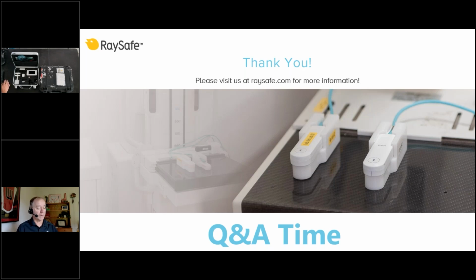But it is versatile enough too, right? So if we have, for instance, a tomo exposure from mammography, there's a setup pulse, and then there's what I call the real part of the exposure, right? And you want to accumulate dose, for example, in both the setup pulse and the real part of the exposure. So you can set the stop delay, which keeps the base unit awake, which actually keeps the system awake, looking for more radiation. So you might want to set that, for example, on a Hologic machine, maybe 6 seconds. So then it captures the setup pulse and the real part of the exposure in one reading or one measurement.